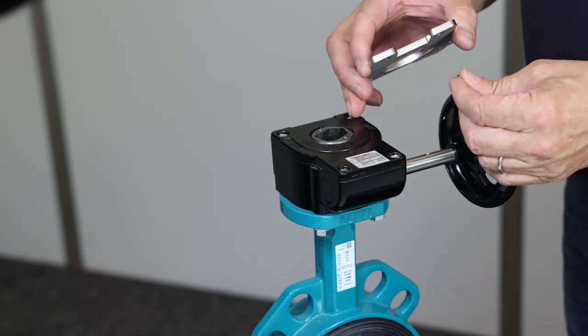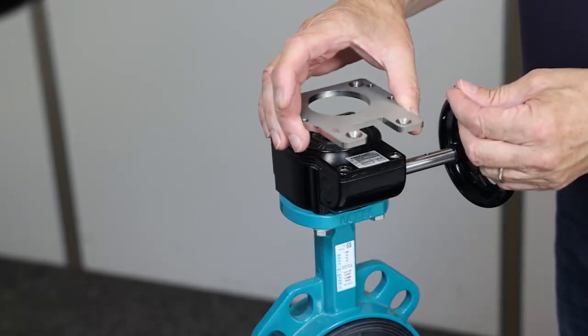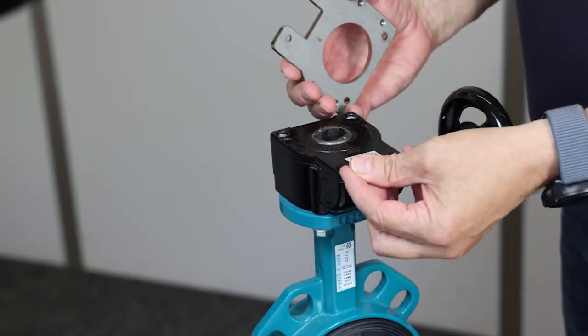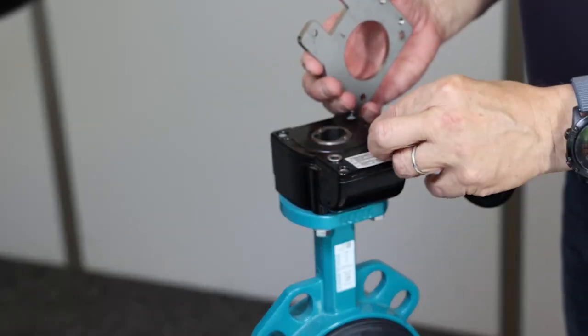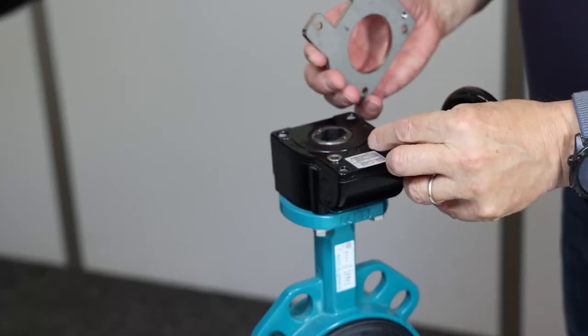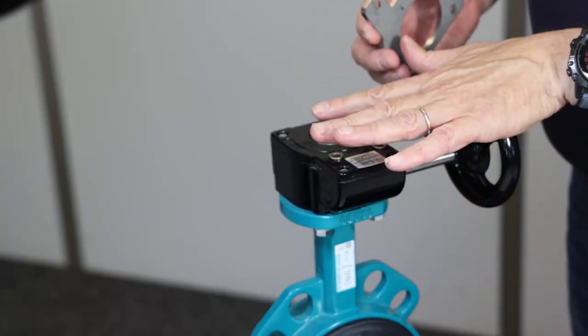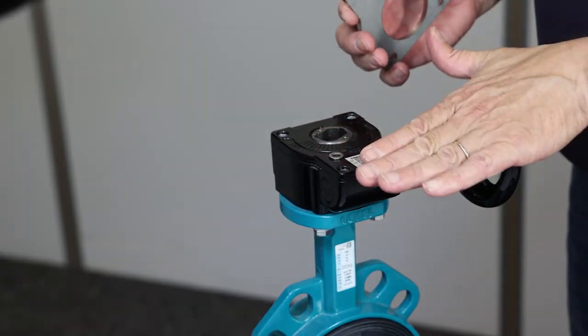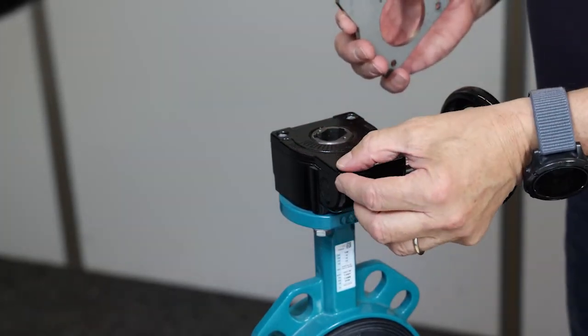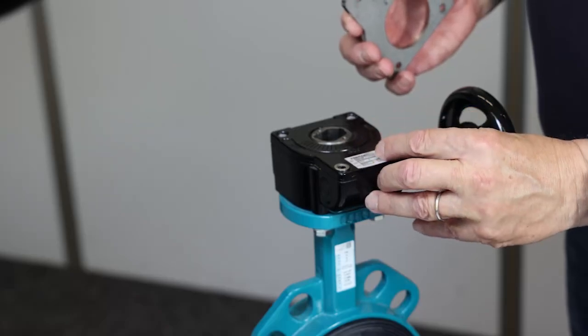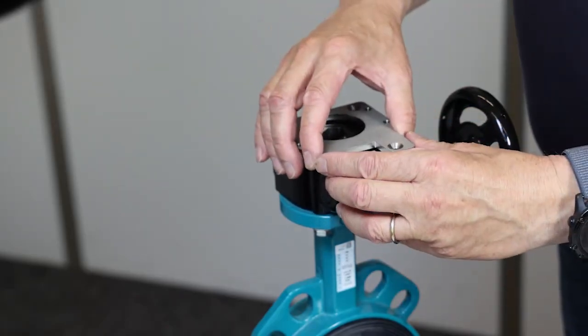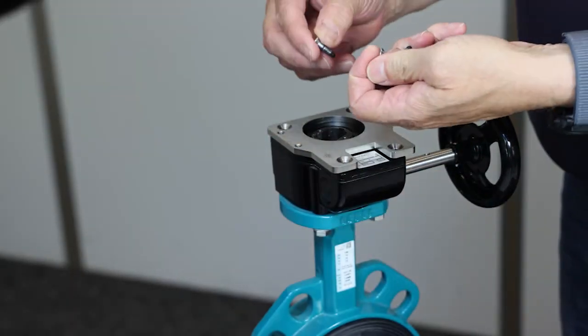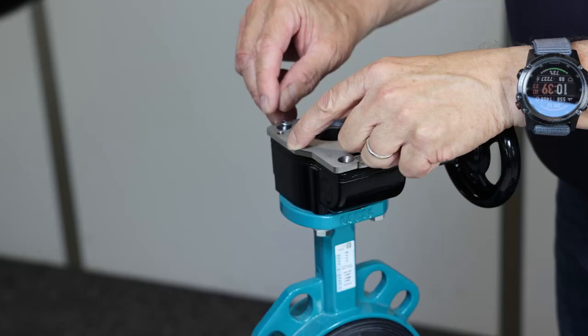As next step I will mount the fixation plate for the limit switch box. First I need to add two washers on the left side to compensate the level of this part of the gear to this part of the gear. This one is a bit lower so I need to compensate with two washers. I take the four screws I removed before.